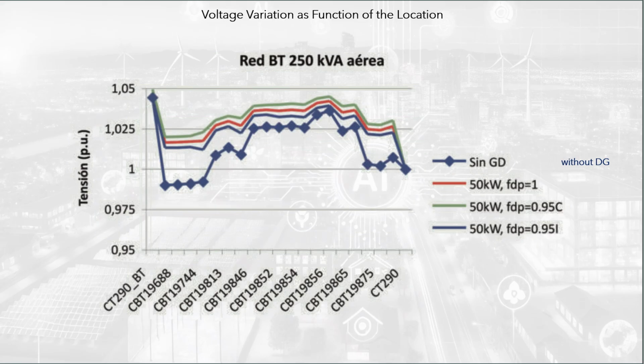Regarding voltage control strategies in the 50 kW distributed DG, the following voltage control possibilities are contemplated. Control with unit power factor, maximum reactive power generation capacity, power factor 0.95 capacitive, and maximum reactive power absorption capacity, power factor 0.95 inductive. As shown in the figure, the injection of active energy into the grid significantly affects voltages. The impact is greater in rural networks than in urban ones, where the impact is very small. As can be seen from the grid associated with the 250 kVA, operating with a unit power factor can cause local overtensions. Therefore, in most operating situations, reactive power absorption by the DG is necessary in order to be able to compensate the overtensions. If reactive power is absorbed at the DG connection nodes, with power factor 0.95 inductive, these overvoltages can be partially corrected.